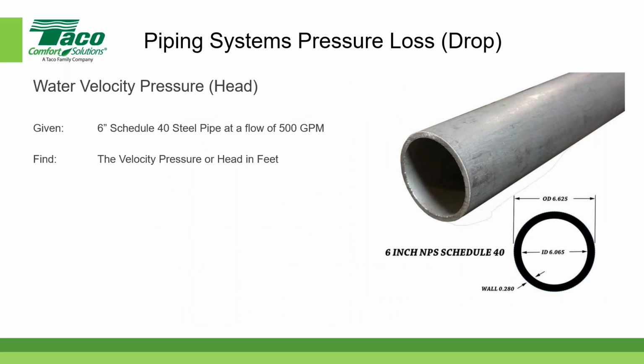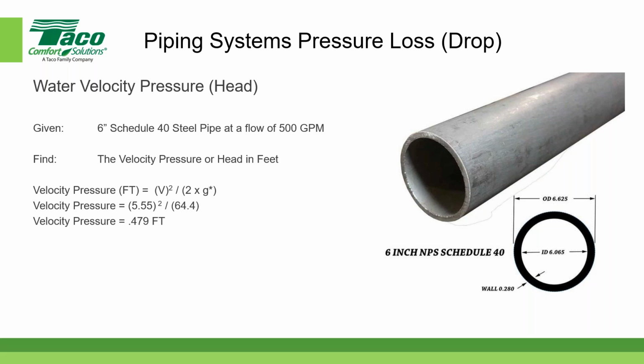All right, so we just did this out, and so the next thing we want to calculate is known as the velocity pressure in head in feet. And the velocity pressure is equal to this equation here that says that the velocity in feet per second squared divided by 2 times the gravitational constant. In our case, we're going to use that same velocity of 5.55 feet per second. We're going to square that divided by 2 times the gravitational constant, which is 64.4. And the velocity pressure is 0.479 feet.